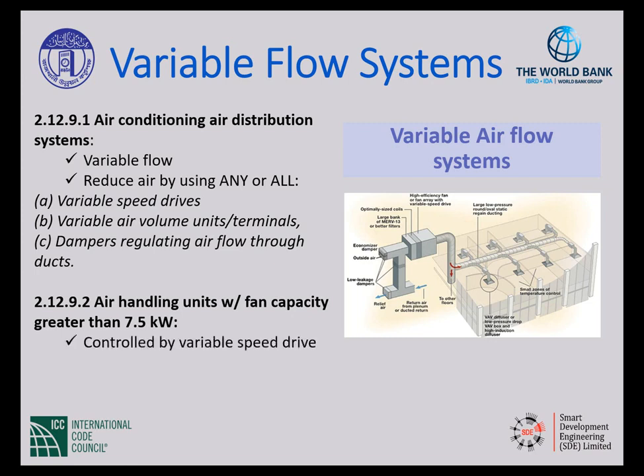And then it says if you have an air handling unit that has a fan capacity greater than 7.5 kW, then it has to be controlled by a variable speed drive. And then there's an exception for kitchen ventilation fans. So variable speed, so it's not just all or nothing. Variable flow, variable speed. You can see this a lot of times, we talk about anything greater than the 7.5 kW fan capacity. Once you get into these bigger fans or these bigger motors that run those fans, then they need to be variable speed. We need to have variable flow on those systems. It's kind of a theme going on, right?